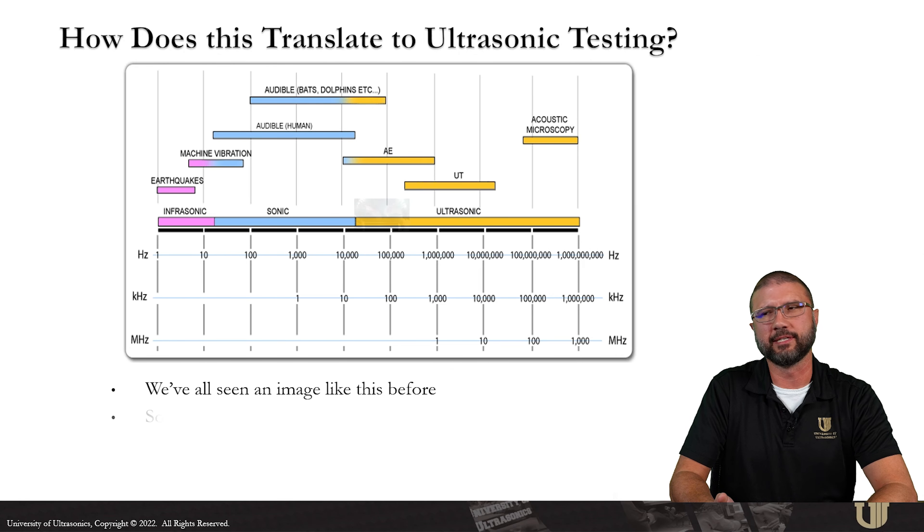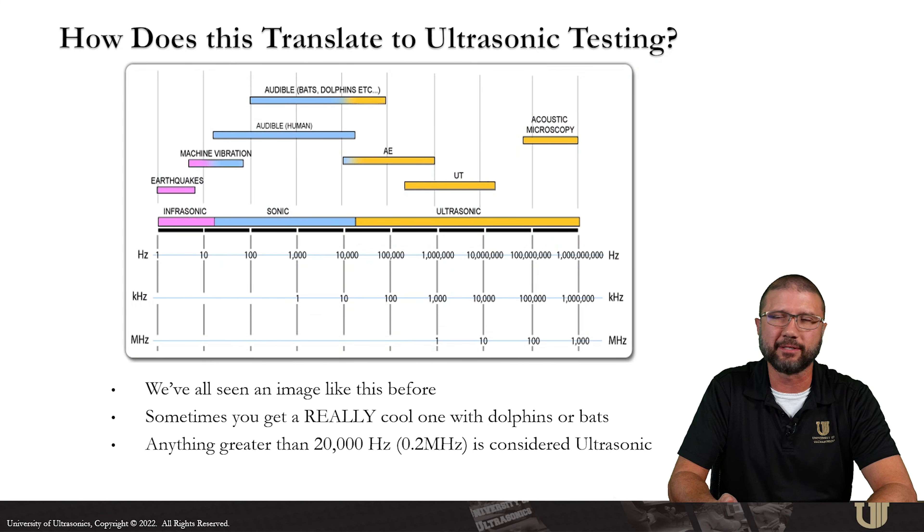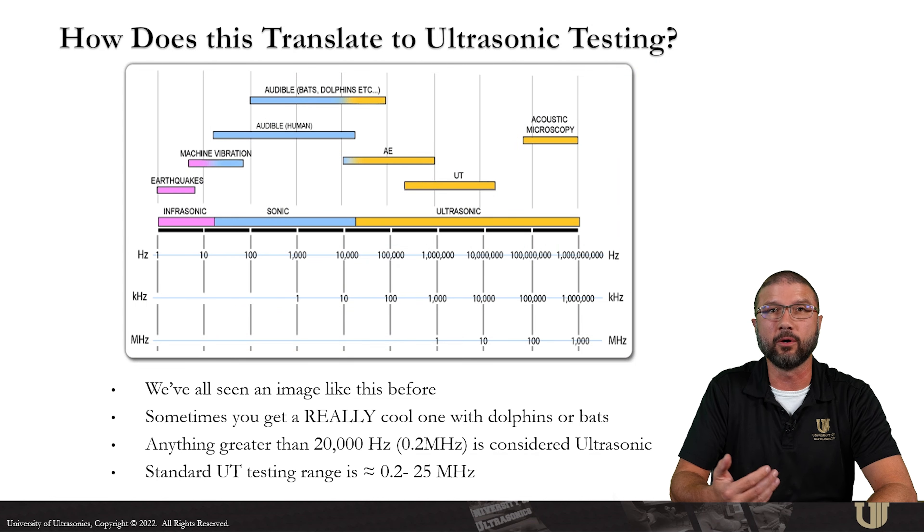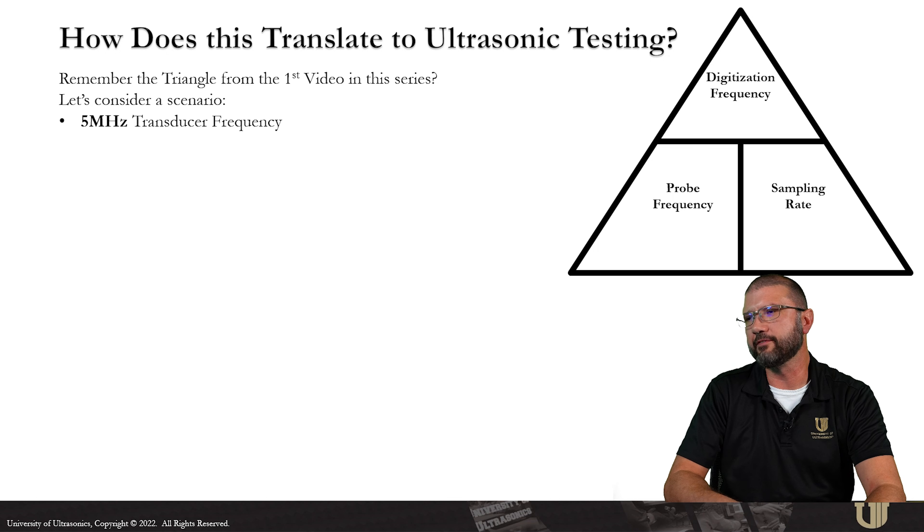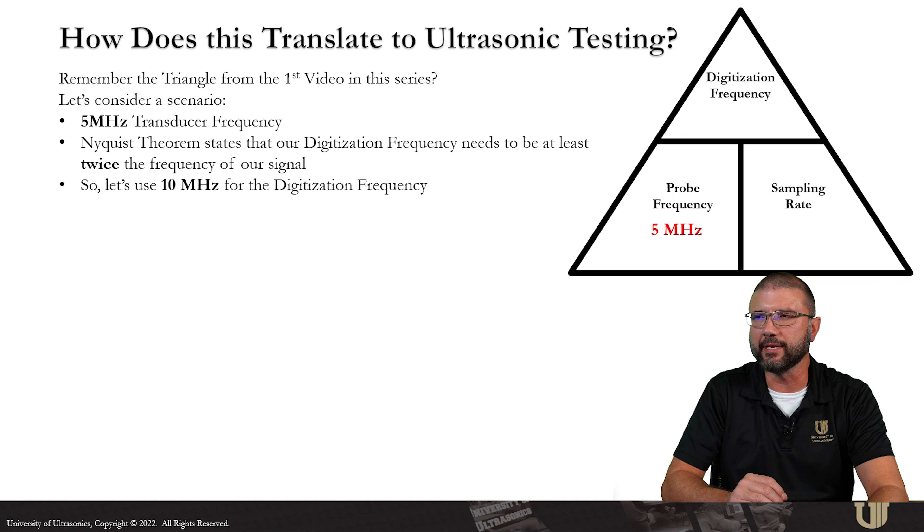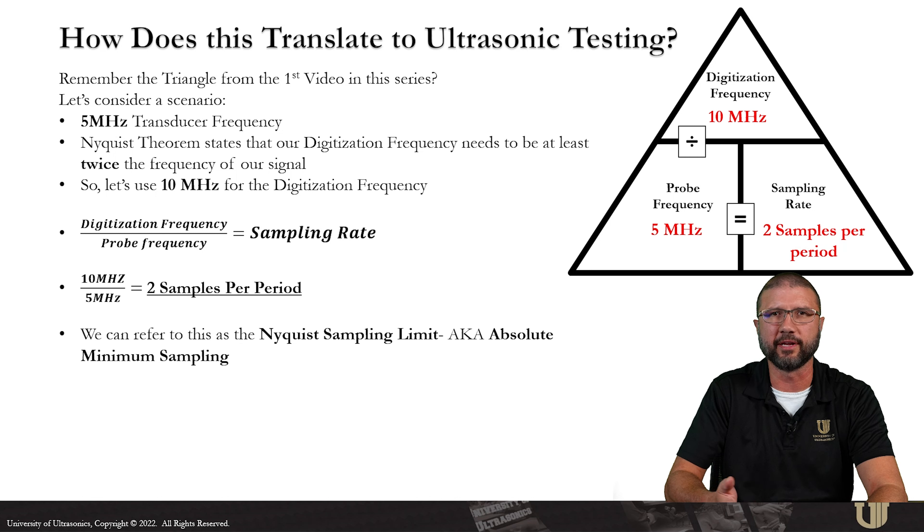How can we translate that to UT testing? That's the big question here. So we've all seen an image like this before. We like to talk about dolphins and bats. Anything greater than 20,000 Hertz is considered to be ultrasonic or just outside of the human hearing range. Standard UT testing is about 0.2 to 25 megahertz. Remember the triangle from the first video of the series and let's consider a scenario. We're going to use a 5 megahertz transducer frequency. Nyquist theorem states that our digitization frequency needs to be at least twice the frequency of our signal. So let's use 10 megahertz for that. 10 megahertz divided by 5 megahertz is going to tell us that we have two samples per period in that scenario. And we can refer to this as the Nyquist sampling limit, aka absolute minimum sampling, two samples per period.